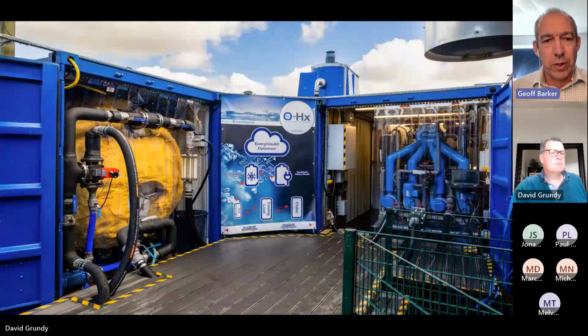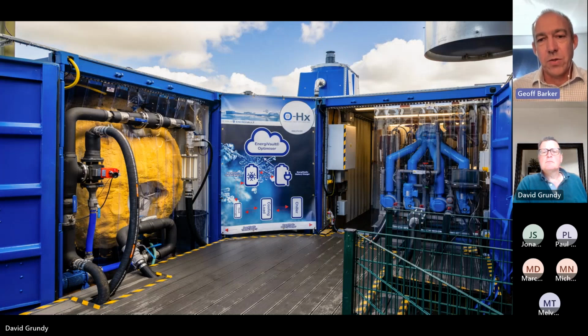So you're going to pull that up again, David. Yeah, so on the right there, the 4 cylindrical elements at the bottom are the end caps of the crystallizers, the evaporators effectively. And you're essentially recirculating the fluid from the tank through those crystallizers to produce this fine crystalline, some people refer to it as binary ice, a very fine crystalline solution of about 60% solids to 30%, or 2/3 to 1/3 solids to liquid. And basically what you have is maybe 0.2-0.3 millimeter small spheres of ice surrounded by the glycol material. So they don't actually bind together, which is one of the key things here.